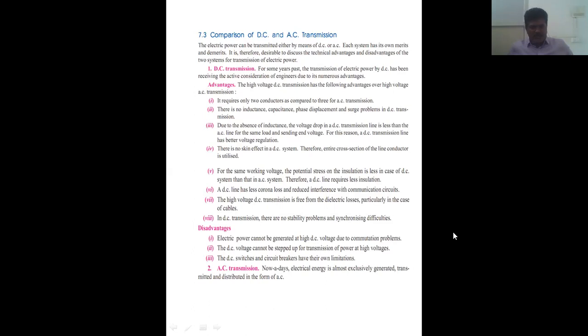DC transmission has the following advantages over high-voltage AC transmission. It requires only two conductors compared to three for AC transmission. There is no inductance, capacitance, phase displacement, and surge problems in DC transmission. Due to the absence of inductance, the voltage drop in DC transmission line is less than AC line for the same load and sending-end voltage.